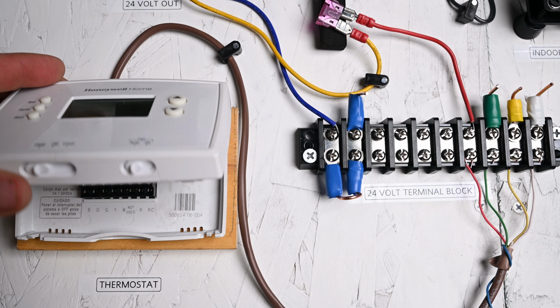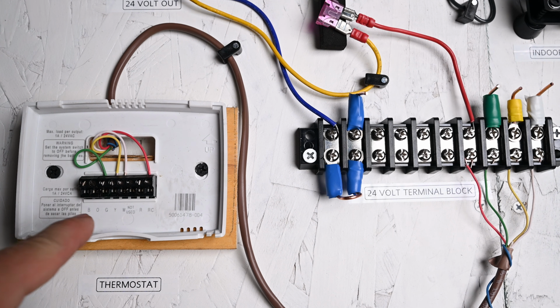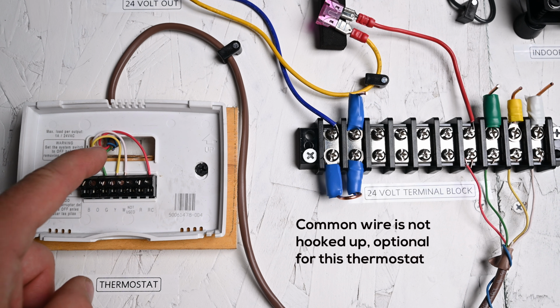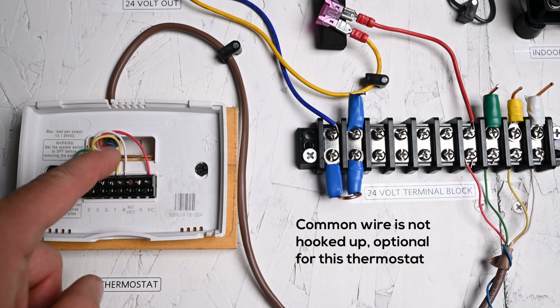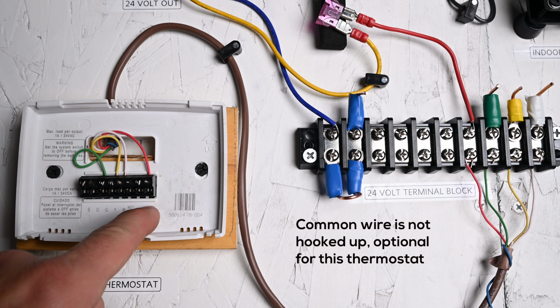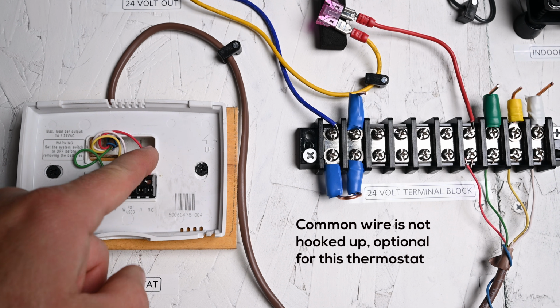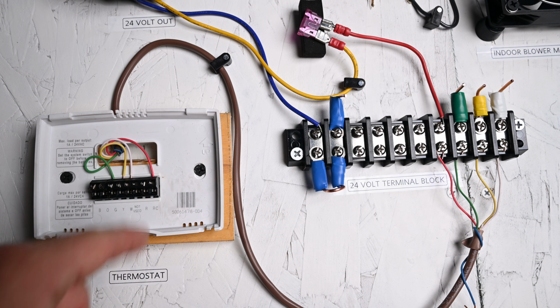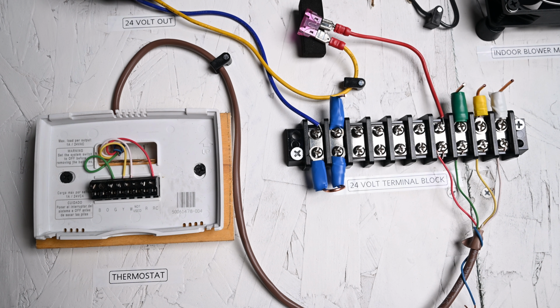Here's how my thermostat is hooked up. You can see we've got G for fan is green, Y for compressor is yellow, W for heat is white, and red, RC, is red. This is our main 24 volt power. Your wiring configuration on the equipment that you're working on may be different. Remember, wires don't care what color they are.